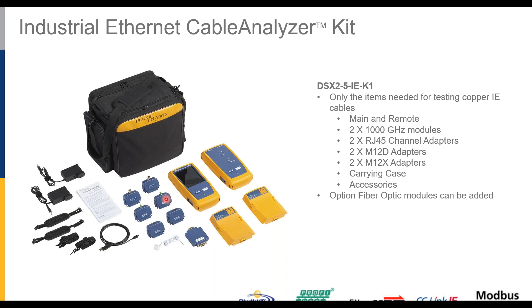Make sure you ask for test results. This will show you that your cabling has been properly installed. Summarizing: follow the standards to make sure your cabling is going to work. Check for that limit on your test report — did they test it to the limit you asked for? TCL measurement will confirm that your system is well balanced and has the noise immunity, and using the right tools will reduce your startup time, and using the right cabling will also make sure it works on the first try.